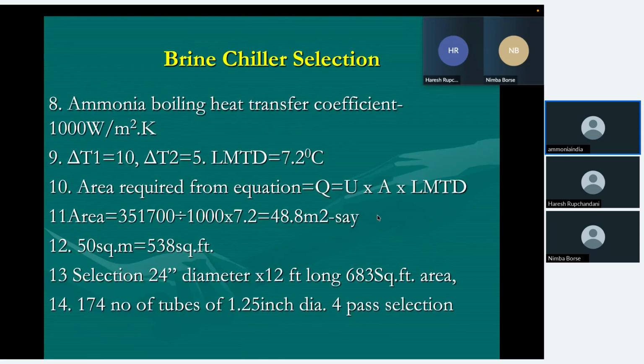Ammonia boiling heat transfer coefficient, as we saw, 1000 watt per meter square. Delta T1 is 10 degrees. Delta T2 5 degrees. So LMTD is 7.2 degrees centigrade. Using the same equation, Q = UA into LMTD, the area required is 48.8 square meter. Let us select a 50 square meter standard chiller.